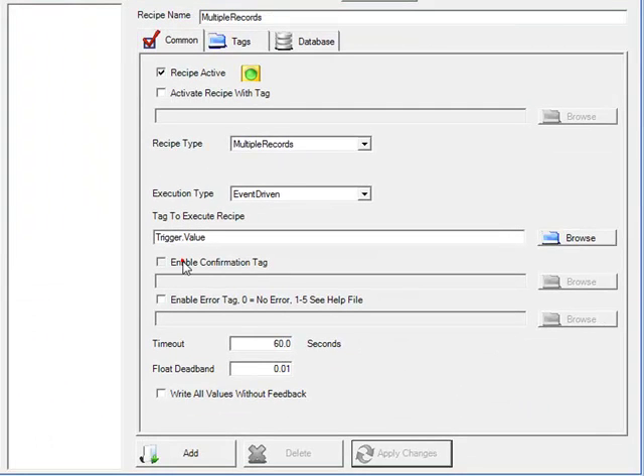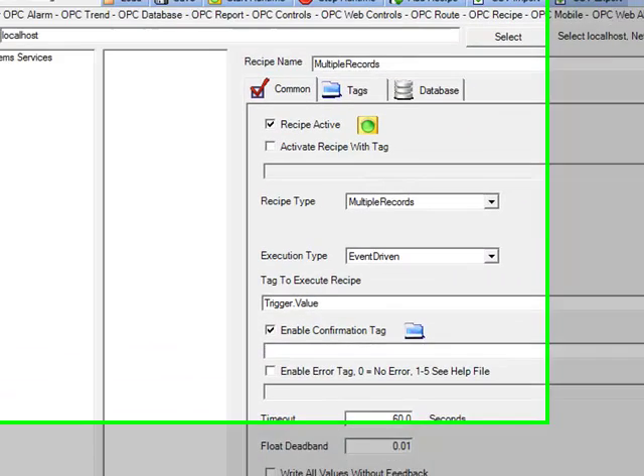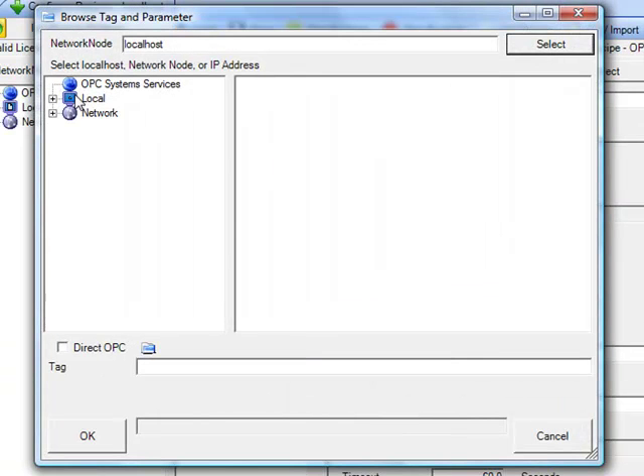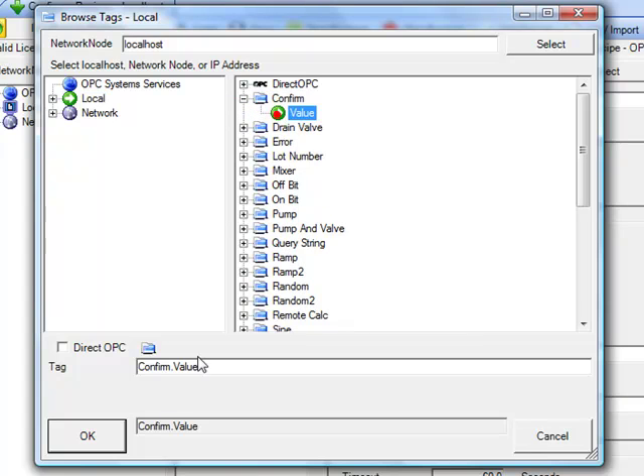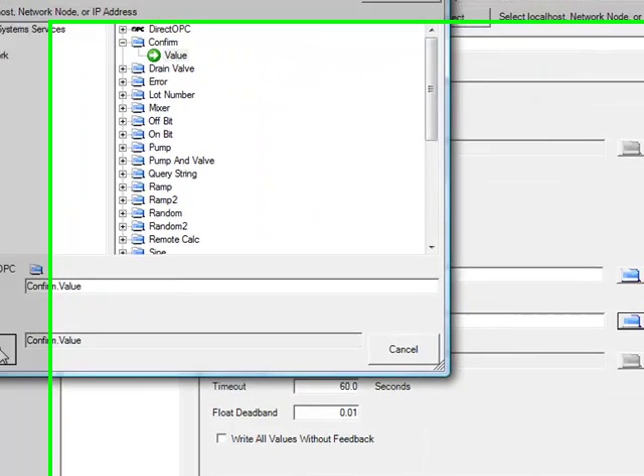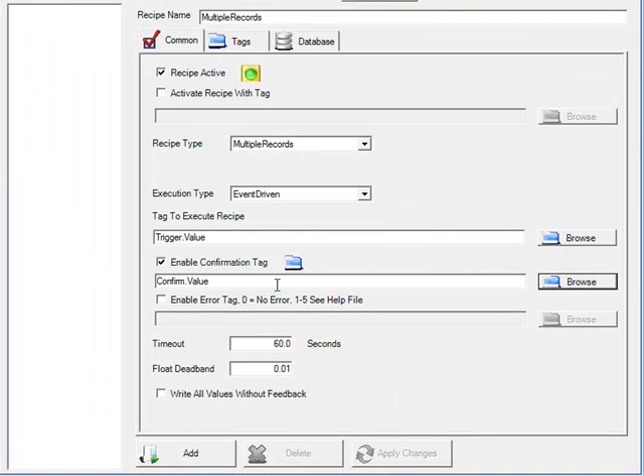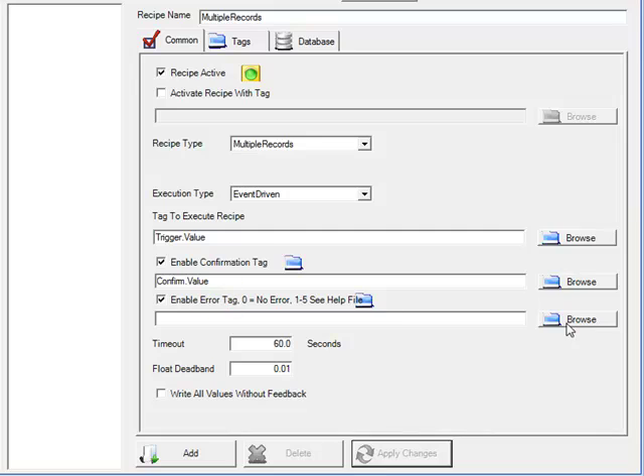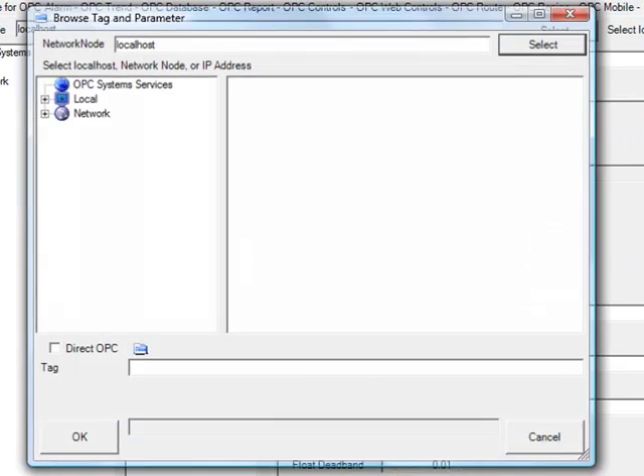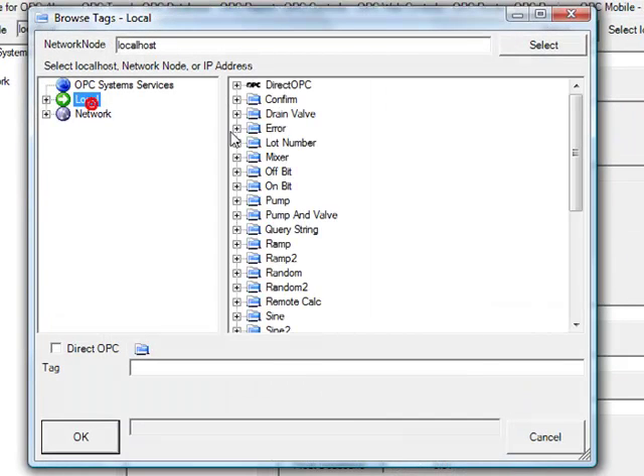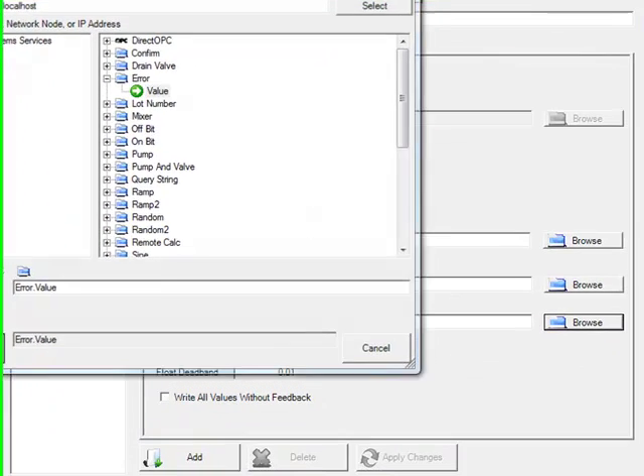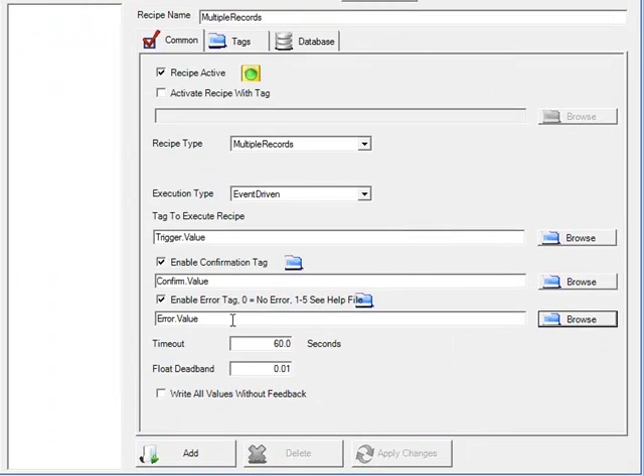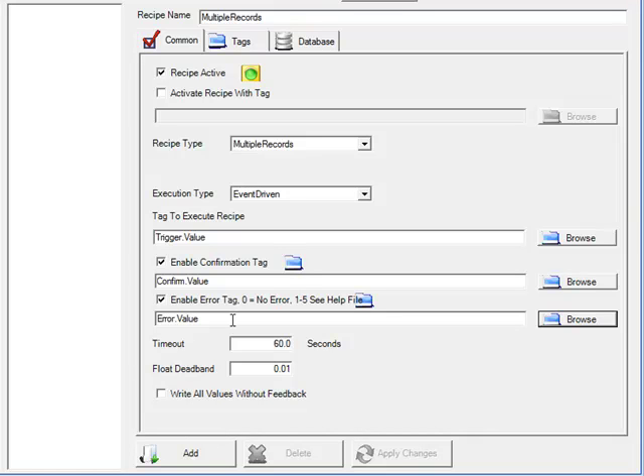We'll also enable Confirmation Feedback, and we'll assign that to the confirm tag with the value parameter, so that when the recipe successfully executes, that tag value will be set to true. Otherwise, we'll enable the error confirmation, and we'll browse for the error tag, and if the recipe execution fails, a numeric value ranging from 1 to 5 will be written to the error tag. In this way, you can have your PLC trigger the recipe execution and then receive feedback with the confirmation tag of being true if successful, or the error tag, which is an integer number, being greater than zero if there was an error.